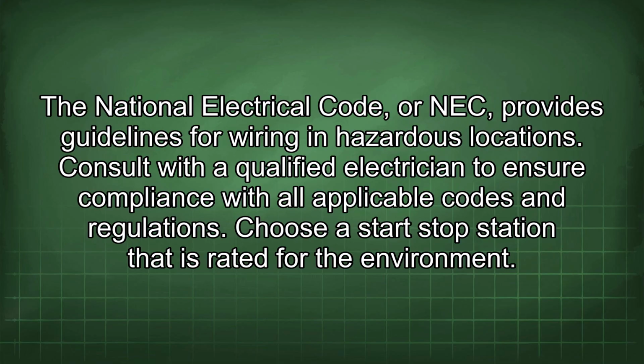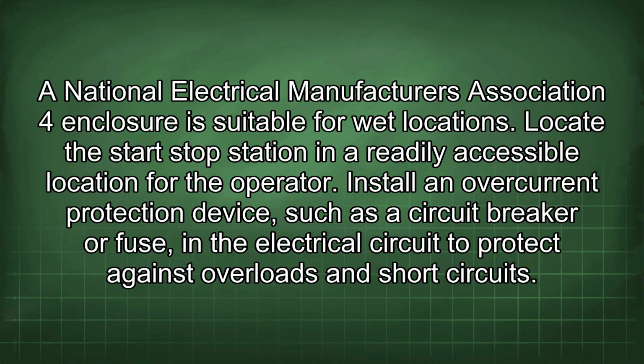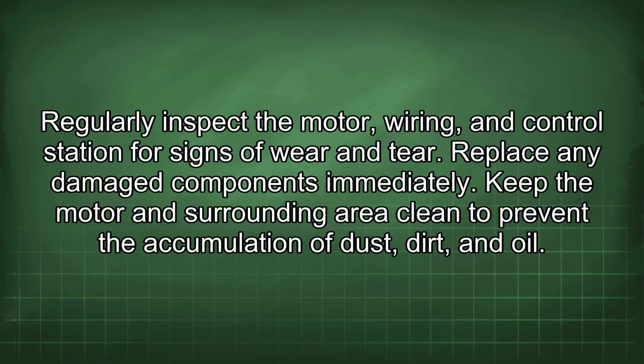Choose a start-stop station that is rated for the environment. A National Electrical Manufacturers Association 4 enclosure is suitable for wet locations. Locate the start-stop station in a readily accessible location for the operator. Install an overcurrent protection device, such as a circuit breaker or fuse, in the electrical circuit to protect against overloads and short circuits. Regularly inspect the motor, wiring, and control station for signs of wear and tear. Replace any damaged components immediately.